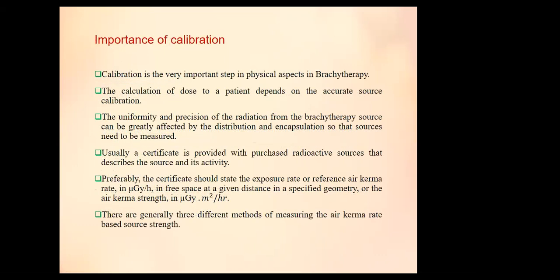So what is the importance of calibration? Calibration is a very important step in the physical aspect of brachytherapy. The calculation of dose to a patient depends on accurate source calibration. The uniform precision of the radiation from the brachytherapy source can be greatly affected by the distribution and encapsulation, so the source needs to be measured. Usually a certificate is provided with the purchased radioactive source that describes the source and its activity. There are generally three different methods of measuring the air kerma rate based source strength.